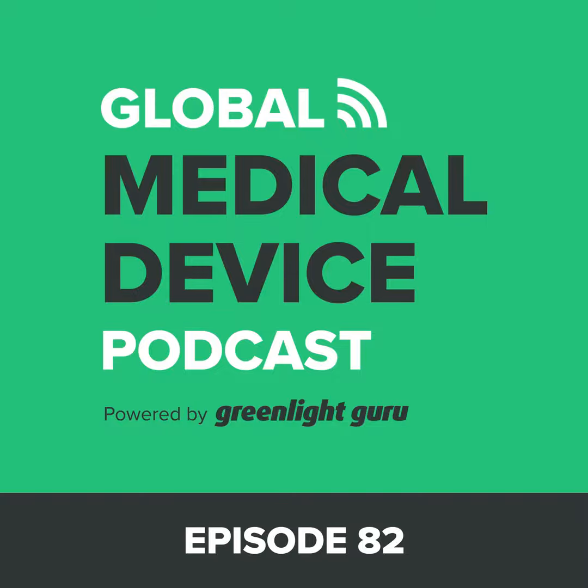Yeah. Well, folks, hopefully this is giving you a lot more insights into the special 510K in general. To Mike's earlier point, probably not anything substantially new with this new guidance or with this new pilot program. Maybe a slight repackaging of things that you should have already been doing to begin with. And maybe the intent behind this is to bring this pathway to your attention. Because as Mike pointed out earlier, if you look at all the different types of 510Ks, about 75% are in the traditional space, whereas the special 510K is about 21%, something around there.